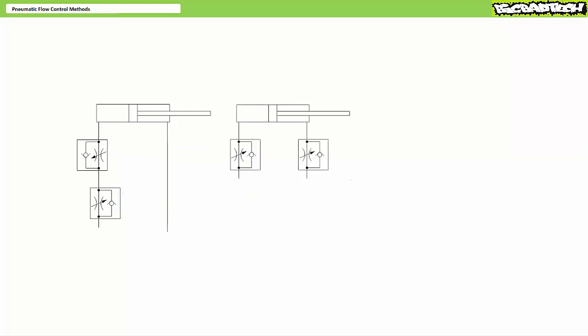Alternatively, one could put a flow control valve on either end of a double acting cylinder. In this configuration, flow control valve one on the cap end establishes a meter in extension arrangement, whereas flow control valve two on the rod end establishes a meter in retraction arrangement.